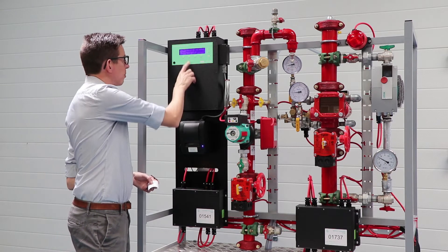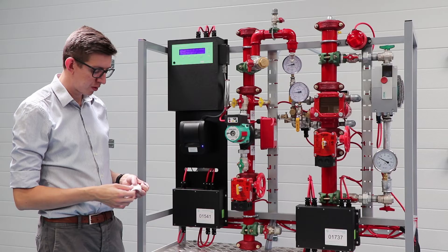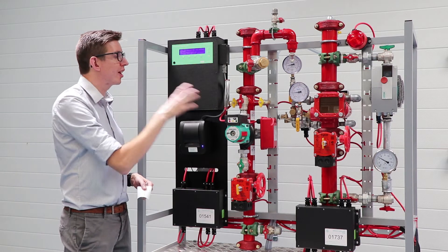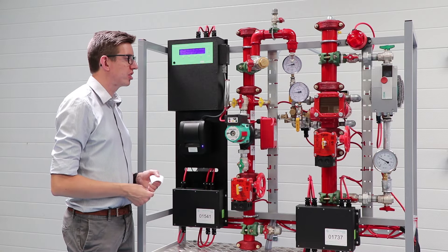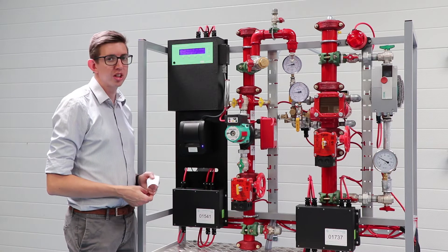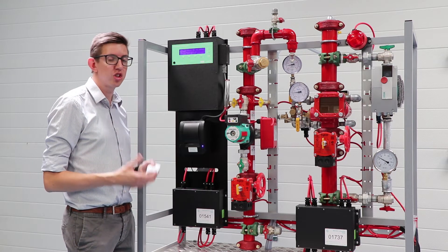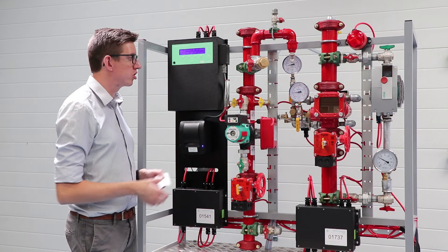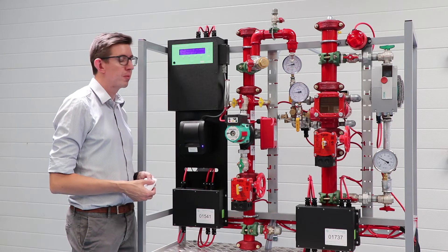As you can see, we've got a pass on our screen. We've now got a digital record of that test and a paper record of that test. We've done all of that test with the push of a button. We've also done that without wasting any water. Traditionally, you'd be throwing away around 630 litres of water, whereas you're probably using about a cup full of water to test it with the Bell Check.